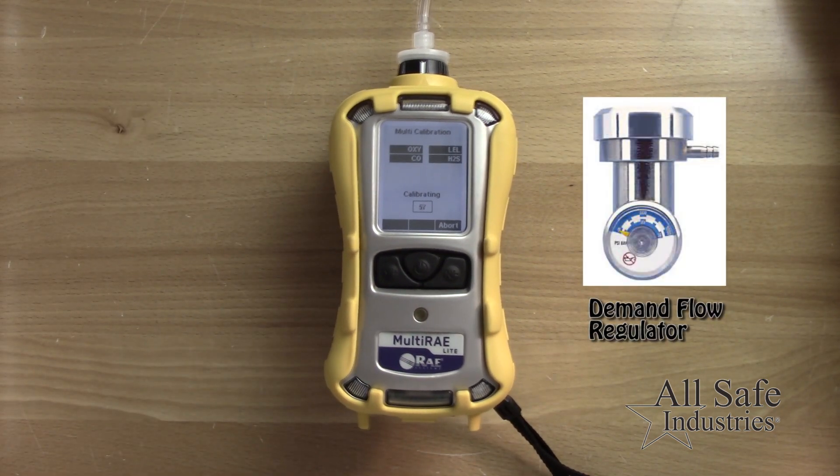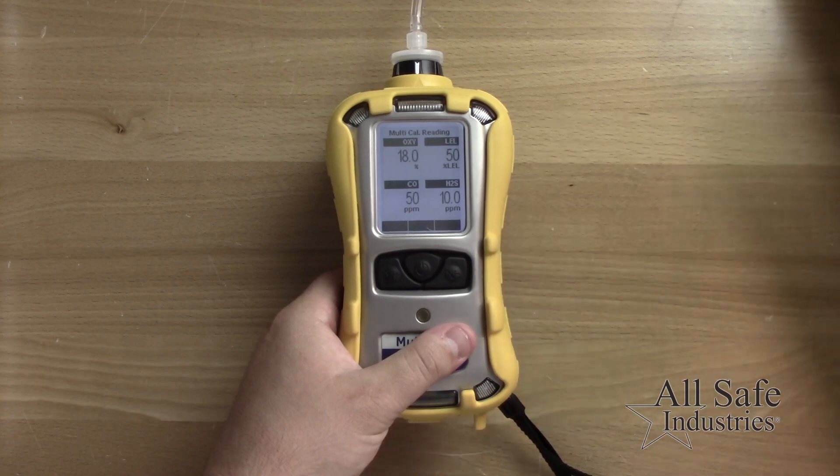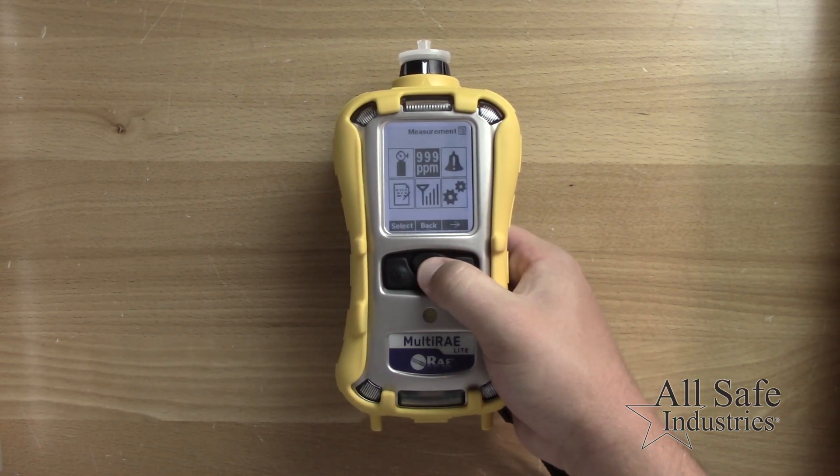You may need more than one cylinder to calibrate all the sensors in your MultiRAE. At the end, the screen will display the values in either a pass or fail for each sensor. Remove the gas and if all sensors have passed, return to normal operation mode.